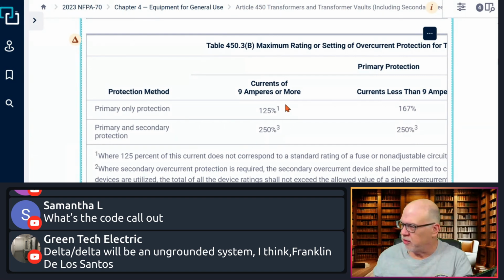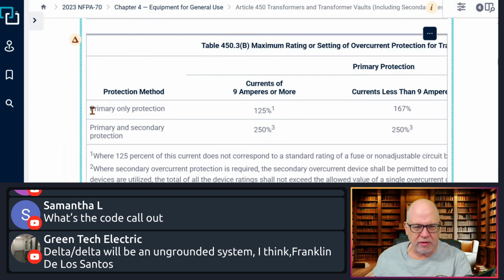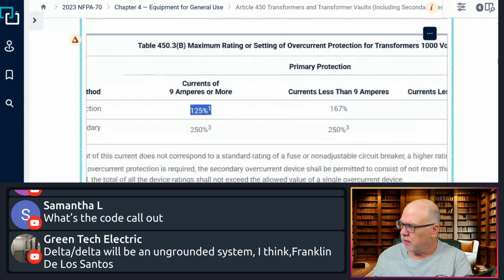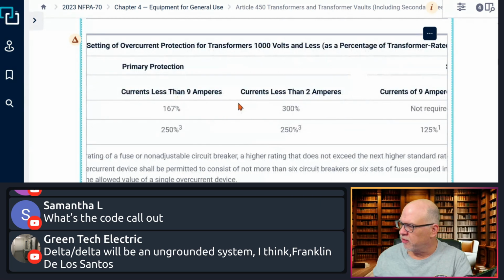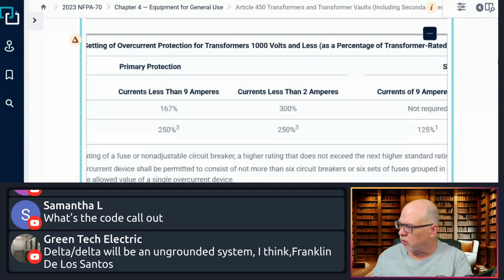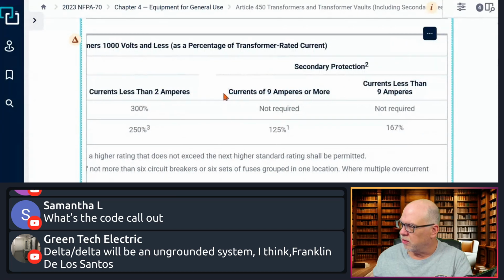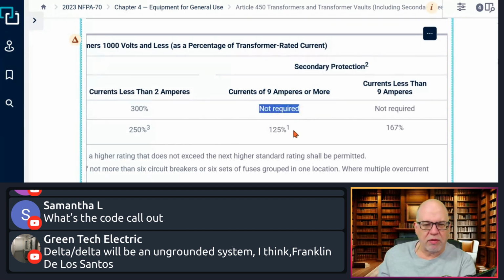And again, you see right here, primary only protection, 125%. If the current is 9 amps or more, then you see here it's not required. Secondary protection is not required for that transformer if we follow these rules.